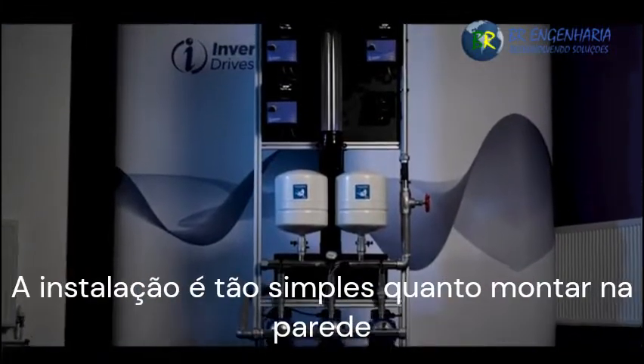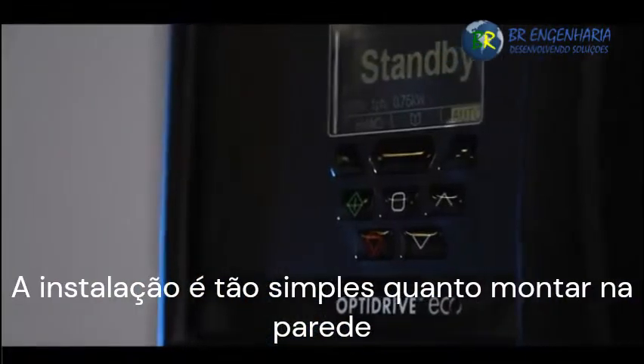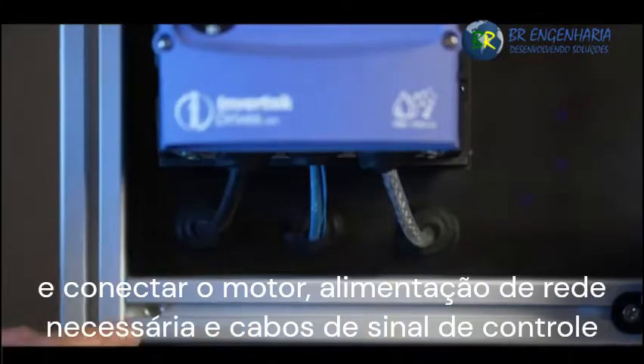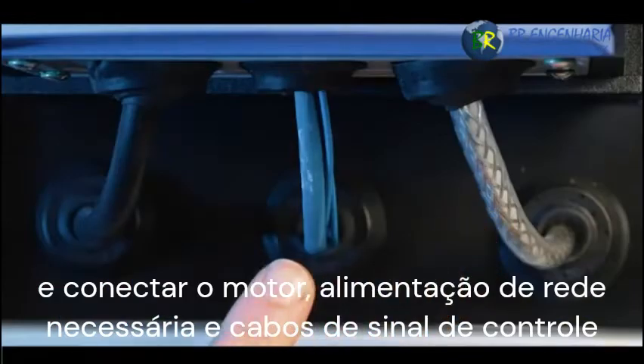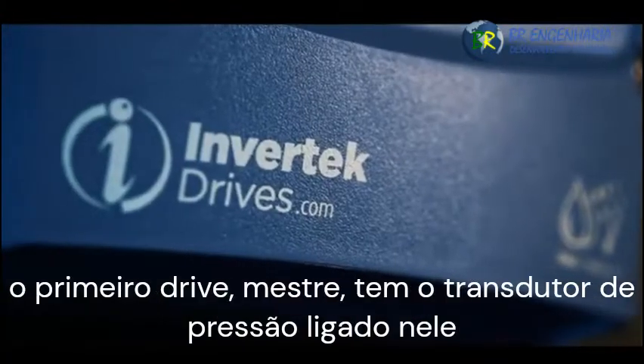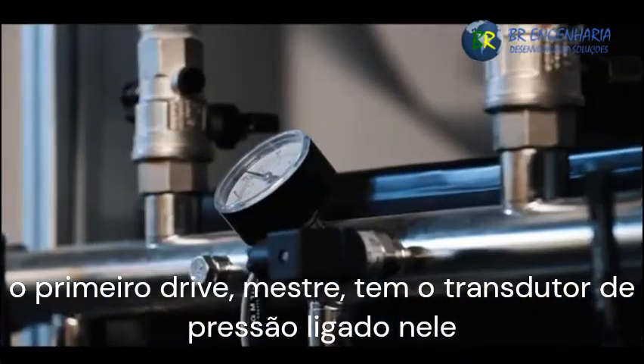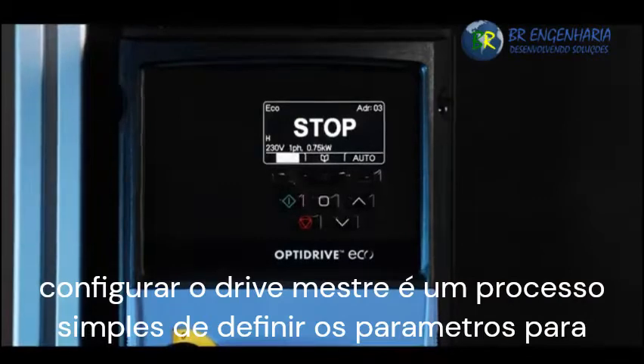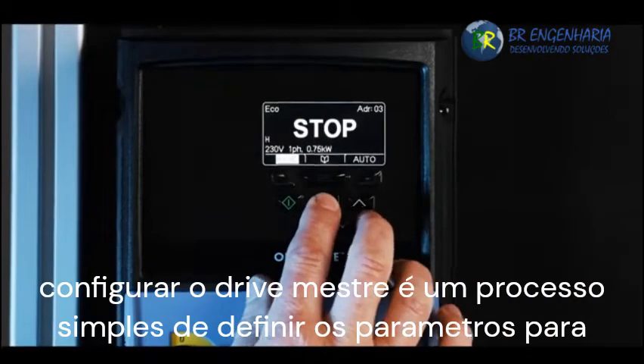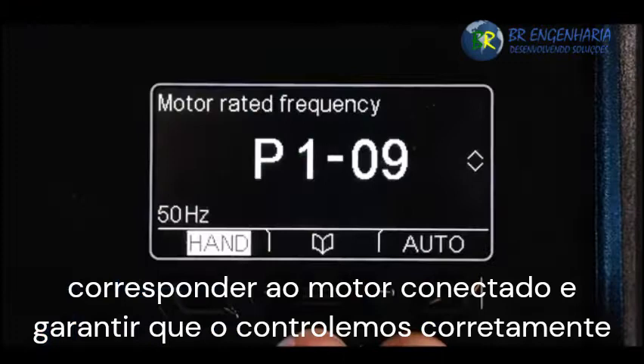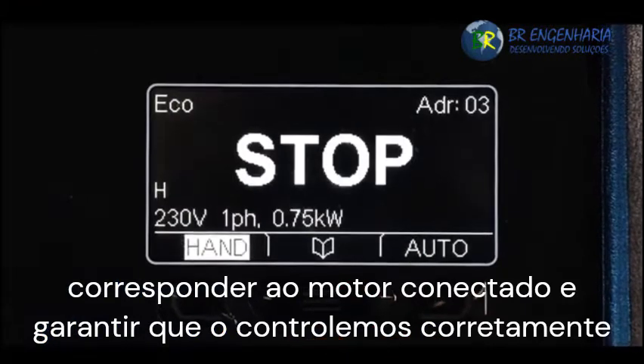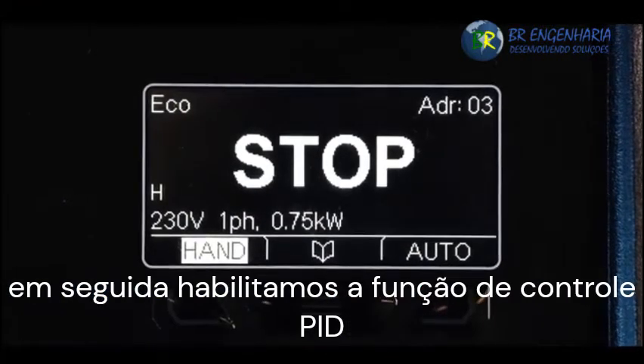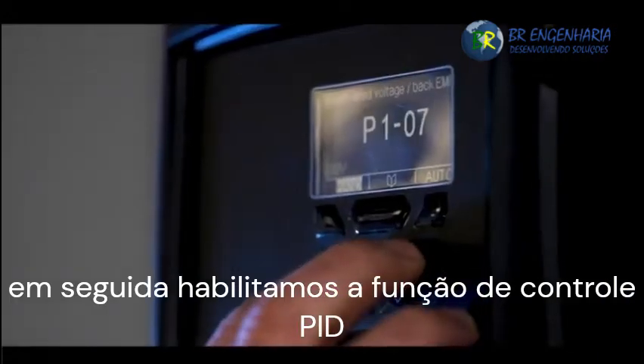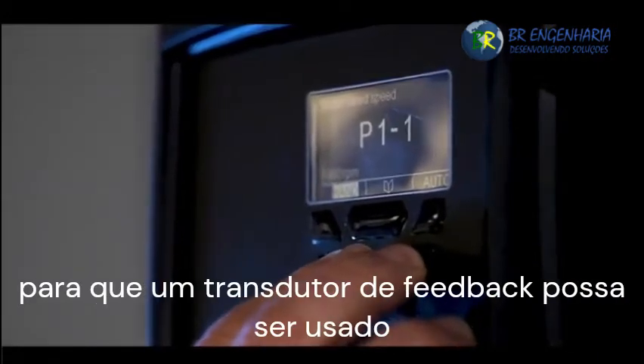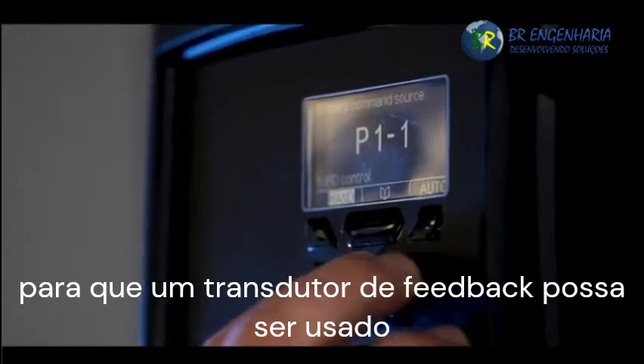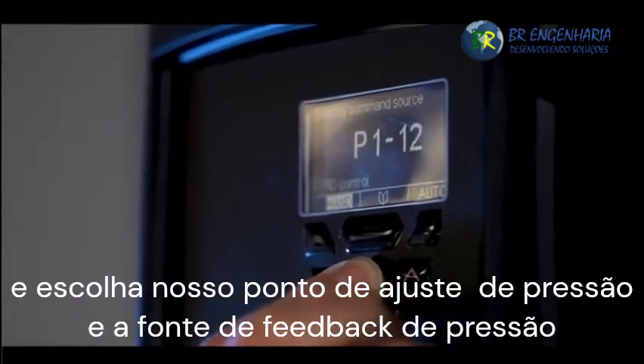the application requires it. Installation of the drives is as simple as mounting on the wall and connecting the required mains power, motor and control signal cables. The first drive, our master, has the pressure transducer connected to it. Setting up the master drive is a simple process of setting the parameters to match the connected motor to ensure that we control and protect it correctly, and then commissioning the drive for the application. In this case, we enable the PID control function so that a feedback transducer can be used and choose our pressure set point and pressure feedback source.